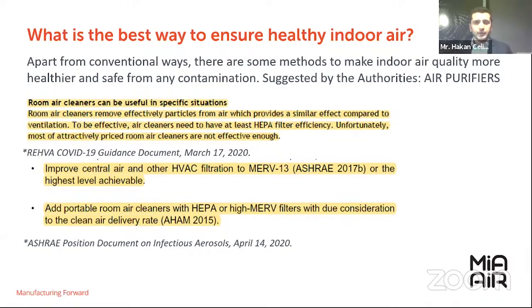To be honest, we wanted to learn and test the other manufacturers' filters. And as per the testing of these filters, we have seen that their filters barely reach the fine class, like mostly F7, sometimes F8, and very rarely F9 class filters. Actually, that is not effective to catch the very fine particles. I'm not even considering the microorganisms, which are smaller than the very fine particles.